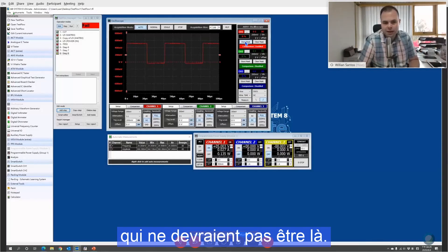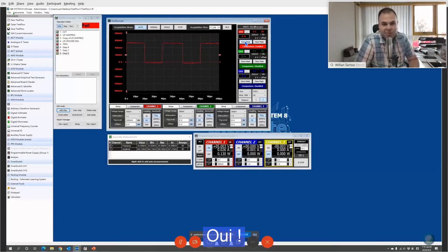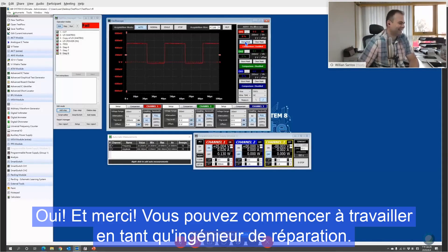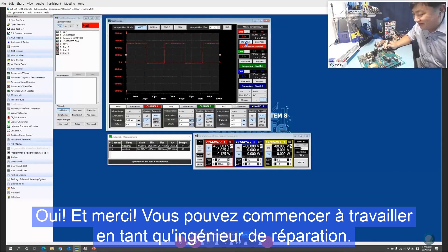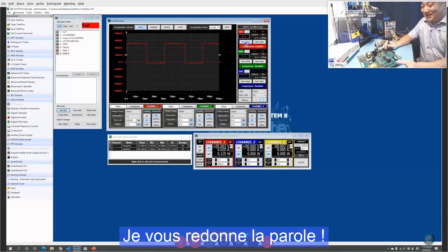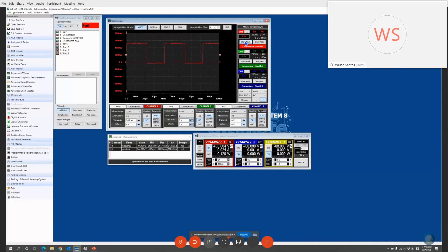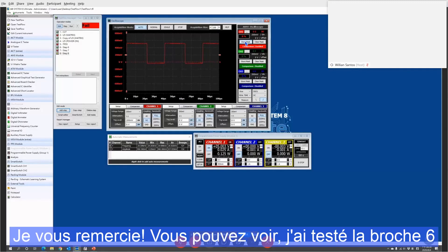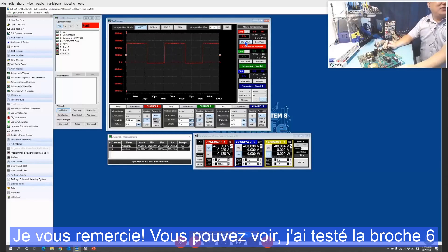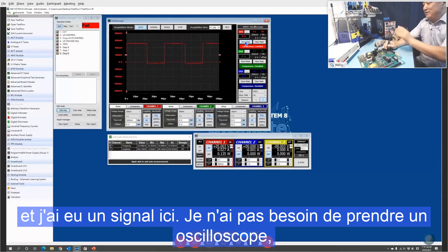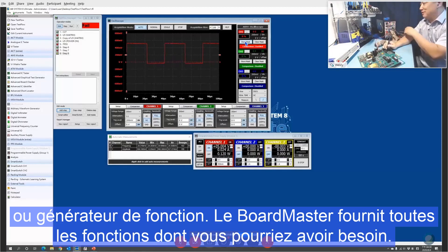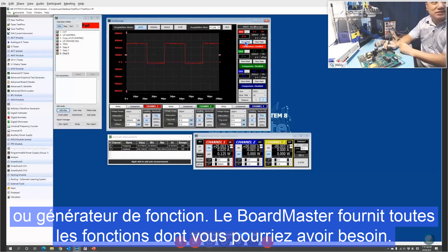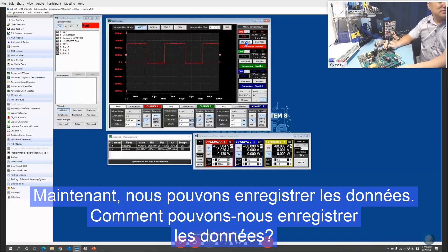There may be interferences that shouldn't be there. So yes, you can see I tested pin 6 and got a signal. I don't need to take another oscilloscope or function generator — the BoardMaster can provide all the functions you need for the repair.